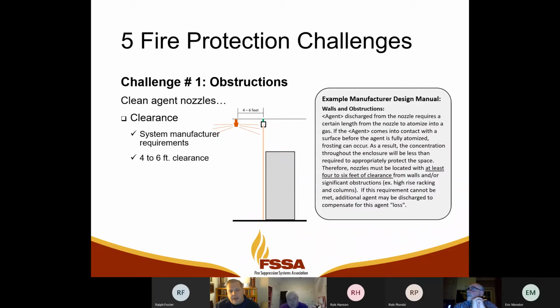Let's see, clean agent. The other thing on clean agents here is clearance. Clean agent nozzles need 4 to 6 feet of clearance from the nozzle before they hit a solid surface to make sure that all the agent flashes to the vapor phase to build an extinguishing concentration within an acceptable amount of time. This is a little bit longer discussion, but since this is an FSSA presentation, I've got to talk gas just a little bit.